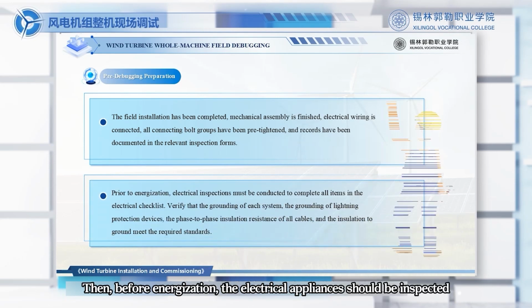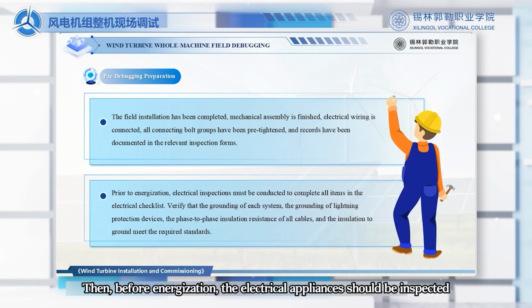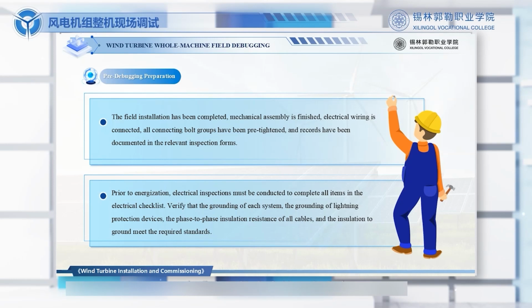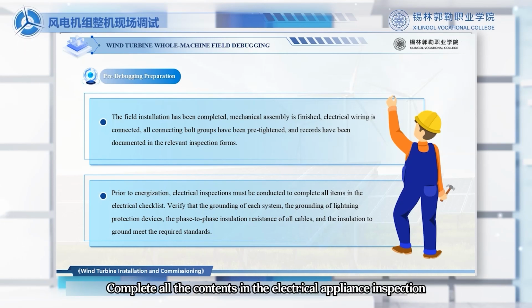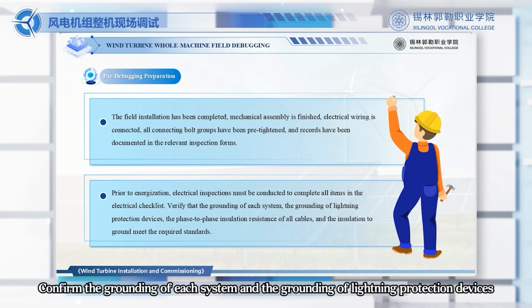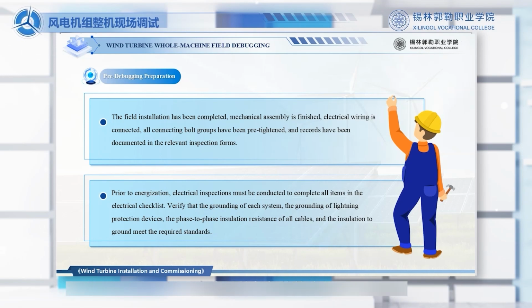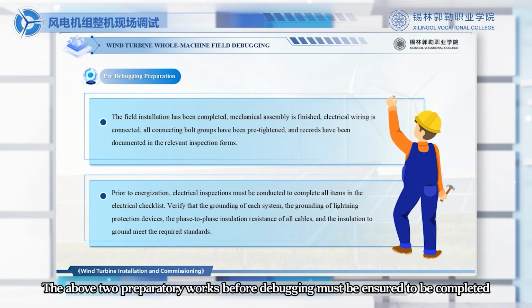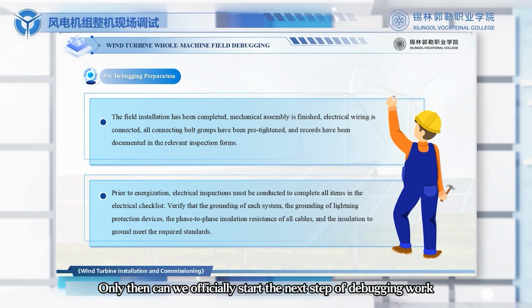Then, before energization, the electrical appliances should be inspected. Complete all the contents in the electrical appliance inspection. Confirm the grounding of each system and the grounding of lightning protection devices. The phase-to-phase insulation resistance and the insulation to ground of each cable all meet the requirements. The above 2 preparatory works before debugging must be ensured to be completed. Only then can we officially start the next step of debugging work.